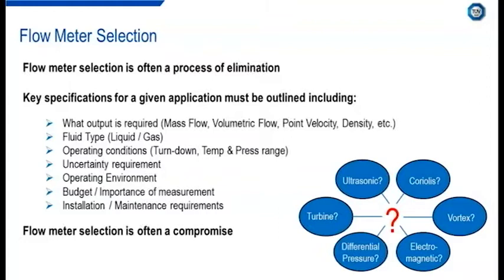The operating environment as well as the operating conditions is important for consideration. Uncertainty requirements often link to the budget available and the importance of the measurement. We may be targeting a very low measurement uncertainty, however the budget and the importance of the measurement may be conflicting. There may not be enough budget to implement the solution that is initially desired for the measurement uncertainty. And also installation and maintenance requirements. So I briefly touched upon installation effects, and these affect different metering technologies, which require different upstream and downstream lengths of straight piping for installation. So the flow meter selection process is often a compromise.